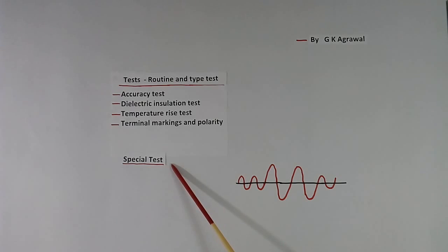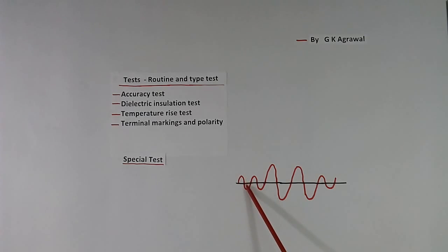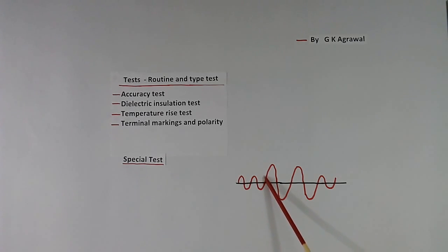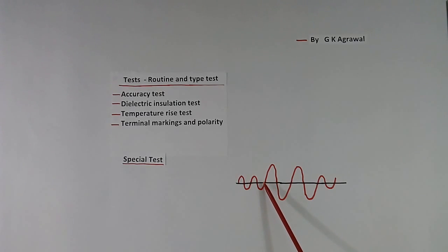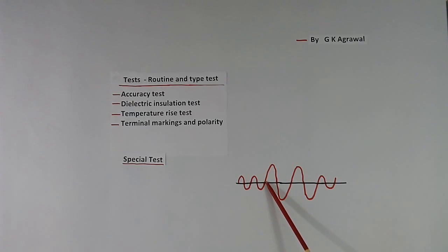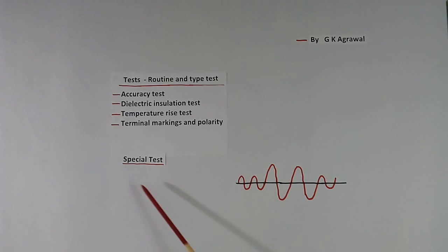Then special tests, if any. For example, here I have shown an AC voltage where the voltage is low, then suddenly goes up, then comes down again. In control applications, we want a fast response, so we check — when voltage goes from low to high, whether the output also responds properly or if there is a delay. That is called the response time test. This is one type of special test; there can be other special tests as well.